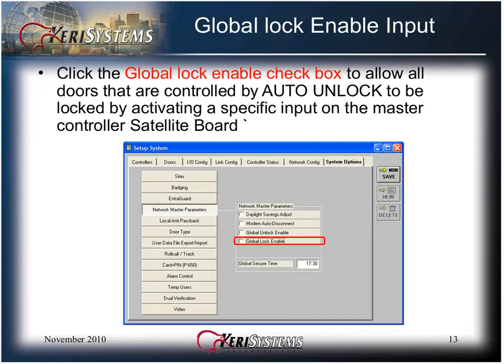Click the Global Lock Enable checkbox to allow all doors that are controlled by an auto unlocked time zone to be locked by activating a specific input on the master controller satellite board. This feature will only lock doors that are unlocked by schedule. Doors that were manually unlocked through software command need to be locked by software command.